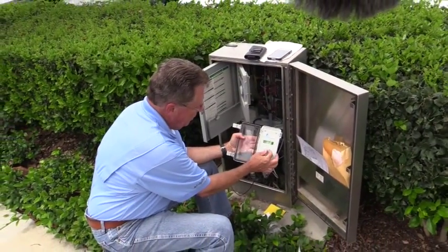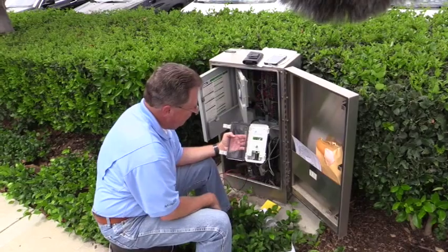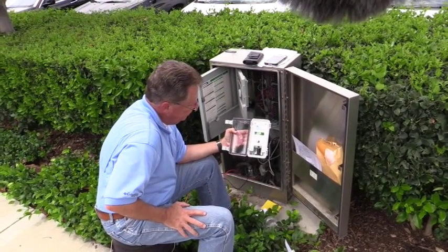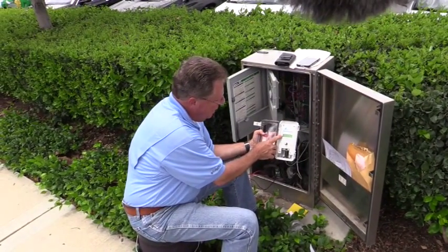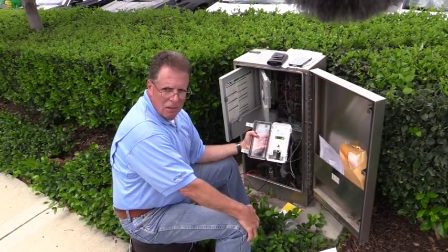Range sensor we're going to set to disable. The last thing it wants to do is a test dial — physically make it communicate. I push the button, and it shows two bars out of four. It says TX for transmission, then changes to RX for receiving transmission, and then it's done — I'm connecting. This thing communicates online, so we're all set. As far as this thing is concerned, I'm done out here. Everything else I need to do, I do on a computer or a tablet.